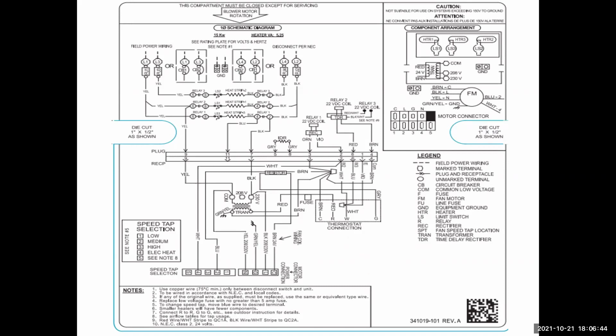So when we come over here, we already kind of talked about walking through and doing the heat. We come over here and here are your motor contacts, terminals. So they have on high heat, for the heat, it's on white, goes up, and it is picking up right here at your Y connection. When there's a call for Y, it's energizing the power to it. On your line voltage side, your first C that you have, that is low voltage common, and that will go ahead and tie in and start up your motor.